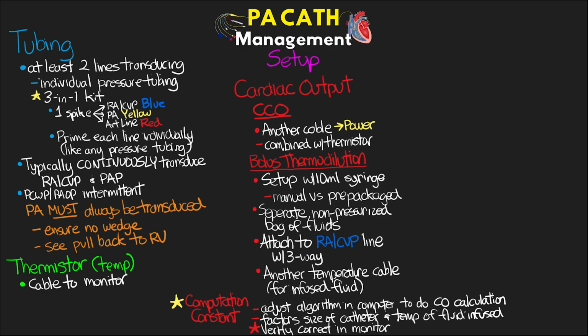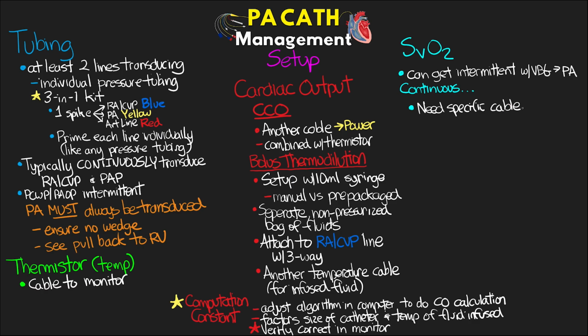All right, now from there, you may also be monitoring a continuous SVO2. So remember that we can get an SVO2 intermittently by drawing a VBG from the PA port. That said, for the continuous monitoring, as you guessed, you're going to need another cable specifically for this. And then once the Swan is placed, we need to calibrate the SVO2 reading to ensure its accuracy. To do so, there's an option to calibrate on your monitor. It's often listed as something like in vivo calibration.